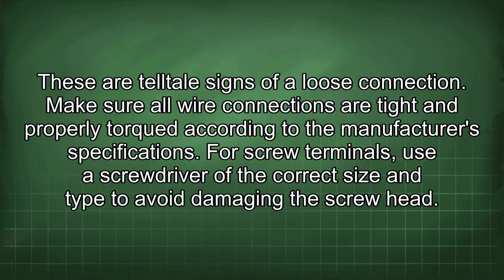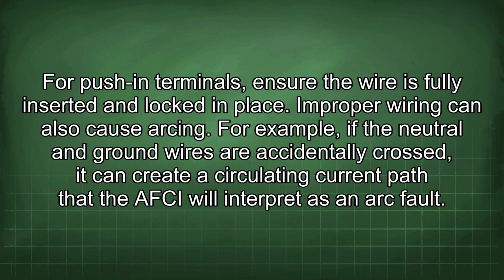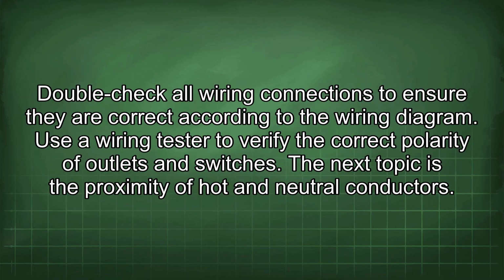Make sure all wire connections are tight and properly torqued according to the manufacturer's specifications. For screw terminals, use a screwdriver of the correct size and type to avoid damaging the screw head. For push-in terminals, ensure the wire is fully inserted and locked in place. Improper wiring can also cause arcing. For example, if the neutral and ground wires are accidentally crossed, it can create a circulating current path that the AFCI will interpret as an arc fault. Double-check all wiring connections to ensure they are correct according to the wiring diagram. Use a wiring tester to verify the correct polarity of outlets and switches.